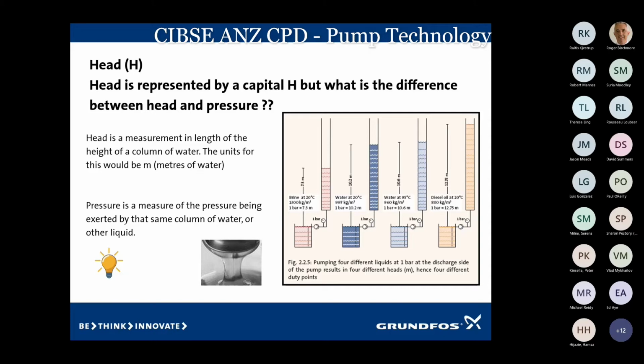If you have to select a pump to pump a product which is a lot cooler than water and denser, and you know that you can't do anything about it, you're stuck with that same pump, keep the pump sitting high up on the curve, at least to the middle of the curve. That way you won't overload the motor.